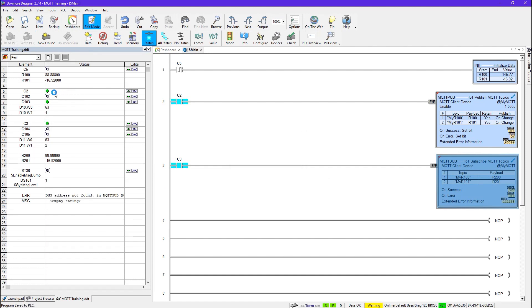So I'm writing that down to the PLC, but now watch what happens right here. Oh, look, see, it failed. And it's telling me error 63 has occurred, and it's telling me that it happened with topic number one.